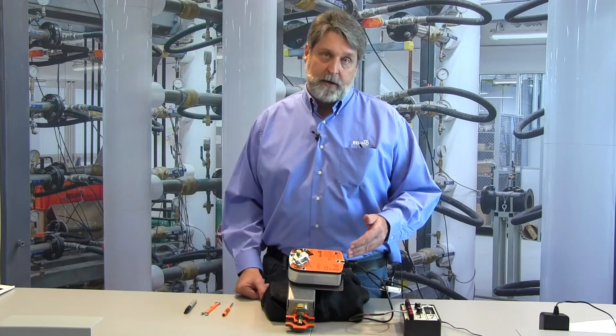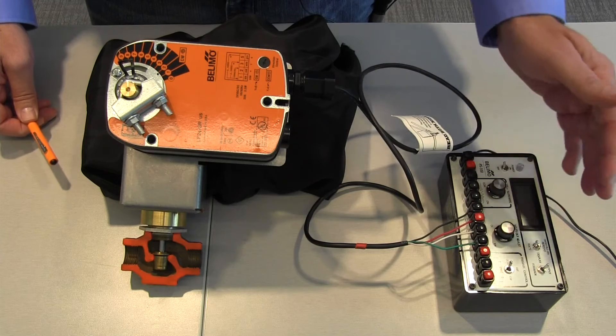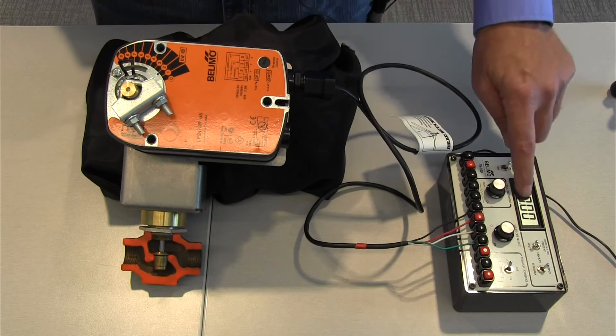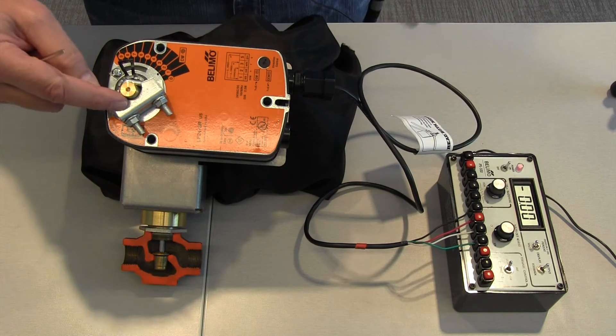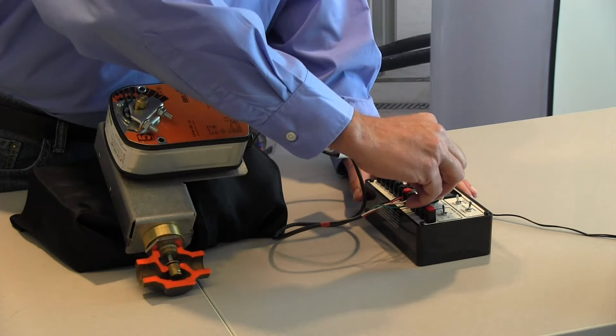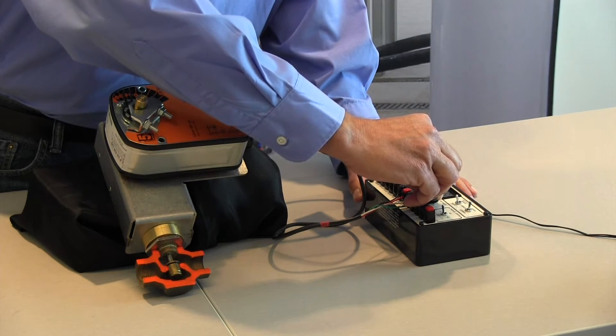I've got the actuator hooked up to the Belimo PS100 power supply. I'm going to turn on the power. I've got it on zero voltage. The actuator doesn't move. I'm going to apply 3.15 volts. The actuator is going to begin to open.